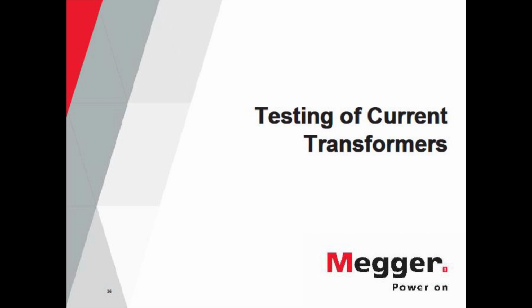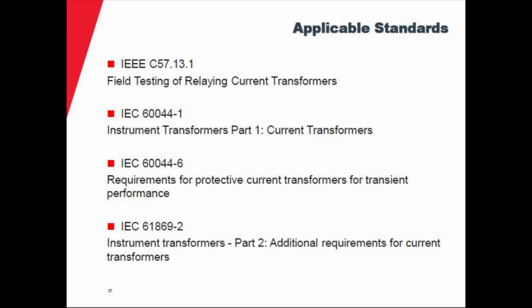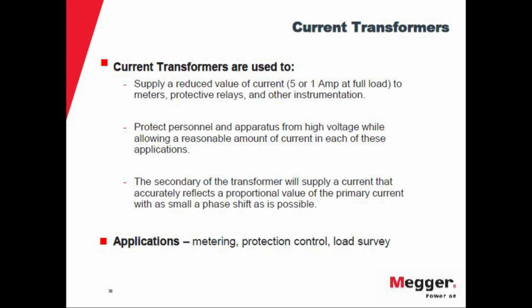Then the next one is the instrument to test current transformers. These are also very common in switchgear or any substation. CT testing has a lot of standards, and the main one is the IEEE C57.13.1, which is the field testing of relay current transformers. And you also have IEC standards for the design and the requirements of these CTs. The current transformers, you use them to reduce the value of a primary current to a magnitude that can be handled by the meters, protective relays, and other instrumentation, so you can do the control of the system. The standard values are 5 amps or 1 amp. The most common one here in the US is 5 amps.